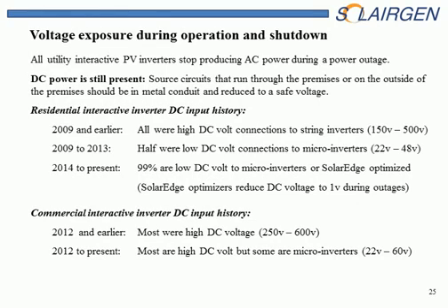Okay, so what is our voltage exposure during a shutdown? We know that the AC power shuts down. All we have to do is pull the meter or whatever. It will stop the AC from producing. DC power is still present, so what are we looking at? Residential interactive inverters, let's do a little history. 2009 and earlier, everything was a string inverter. They operated somewhere between 150 volts to 500 volts. Now we're talking about interactive systems here. That's a pretty high voltage. That has the potential to electrocute, has potential to create a fire. So that's 2009 and earlier.